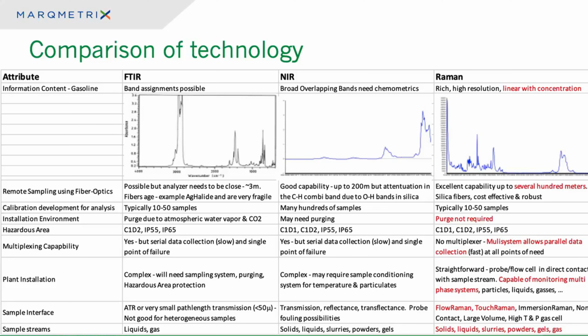I'm going to touch lightly on the comparisons of technology. I've highlighted a few things. We'll focus on the Raman side. Just a simple comparison between the vibrational techniques of FTIR, near IR, and Raman. One of the key distinguishing points between Raman, as I mentioned earlier, is we're linear with concentration. We don't have a specific range in which our calibrations are good. We are good from basically our limit of detection up to 100%. It gives us rich, high resolution information. We're also able to basically extend the capability. And we've done over a kilometer in some installations, but in many cases we use several hundred meters of fiber optic to displace the box from the actual sampling point.